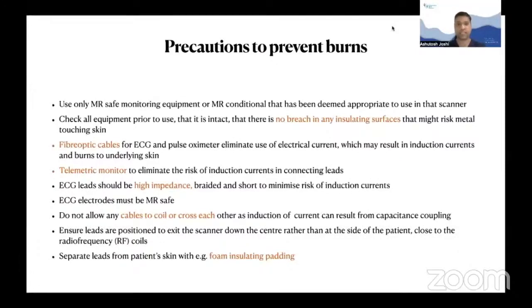Fiber optic cables for ECG and pulse oximetry eliminate the use of electric currents, which may lead to induction currents and burns to the underlying skin. Telemetric monitoring is advisable as it eliminates the risk of induction currents. The ECG leads should be of high impedance. Do not allow any cables or coils to cross over, and use foam insulating padding on the patient's skin wherever you suspect the cables may touch.